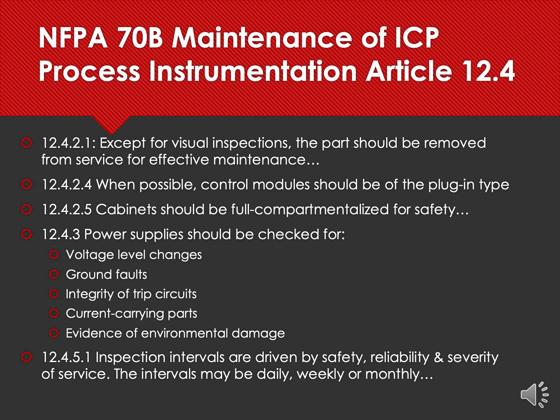Ground faults in the system, of course, need to be identified and isolated. An important thing to consider with ground faults is depending upon the impedance or the resistance of the fault, it is possible for a ground fault to develop and it will not actually trip the system out of service. In those situations, you can have an ongoing shock hazard where a piece of equipment, the frame of a piece of equipment gets energized and stays that way. And of course, those things need to be cleared immediately in the system. The integrity of the trip circuits also needs to be checked and verified and maintained to make sure that if there is a trip in the system, that it expeditiously trips the system out of service.